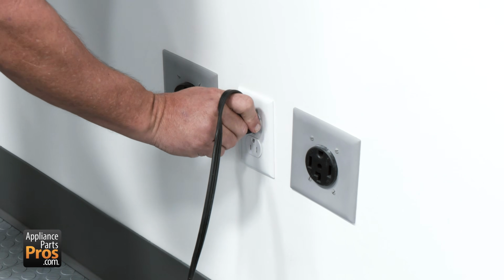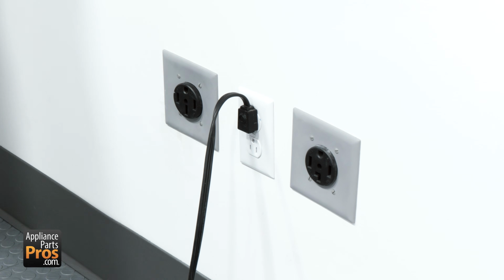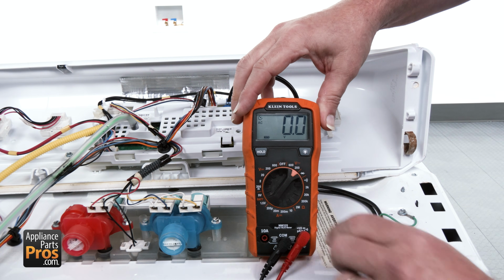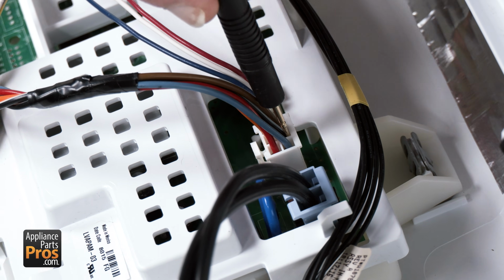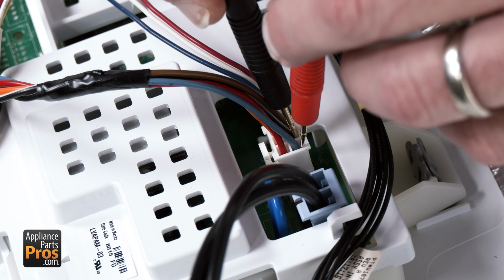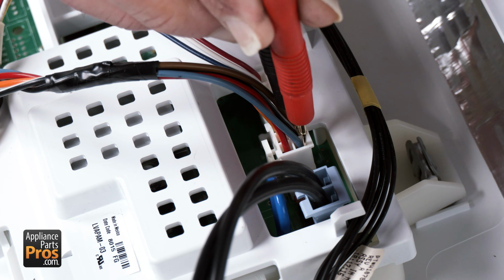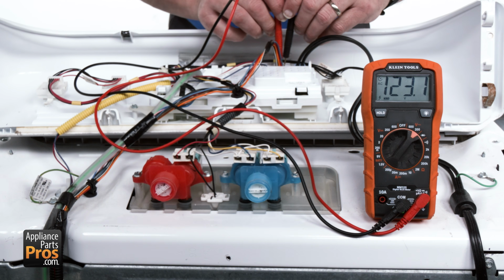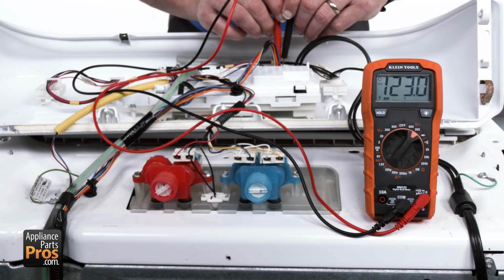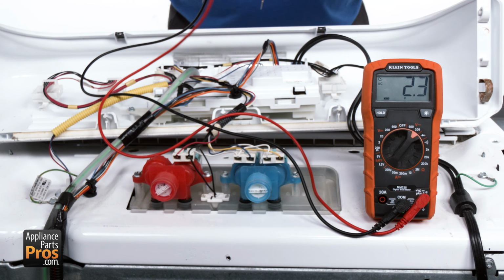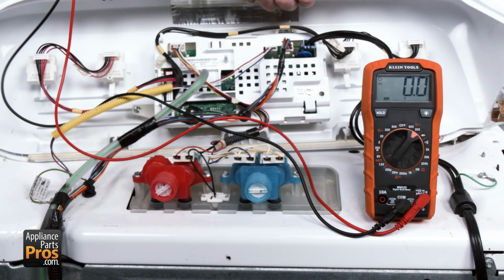Then reconnect power and test the incoming voltage at the control. With your meter set to AC volts, check between J2 pin 2, L1, and J2 pin 3, neutral. You should read approximately 120 volts AC. If voltage is present, but the drain pump is not running, then this would be a faulty drain pump that would need to be replaced.